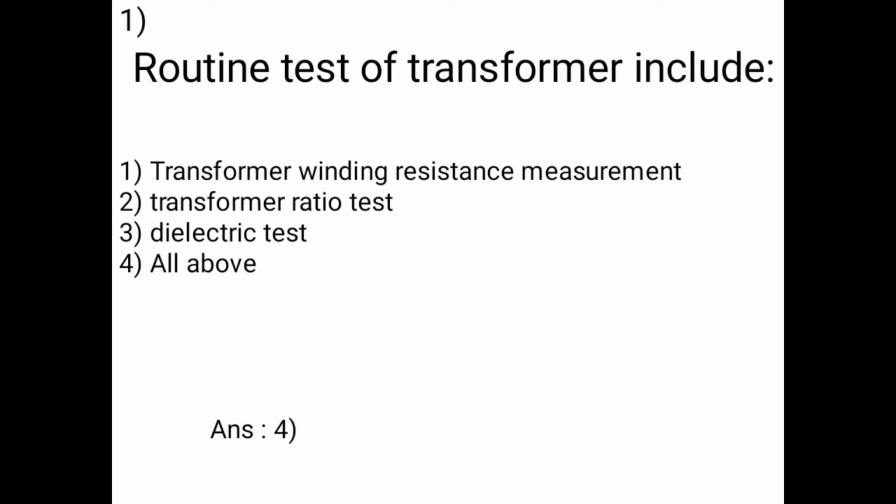Today our topic is MCQs on Unit 4, 5 and 6 of Maintenance of Electrical Equipment. The first question: routine tests of a transformer include which of the following? Options are first, transformer winding resistance measurement, second, transformer ratio test, third, dielectric test, and fourth, all of the above. So the routine tests of a transformer include all of these.